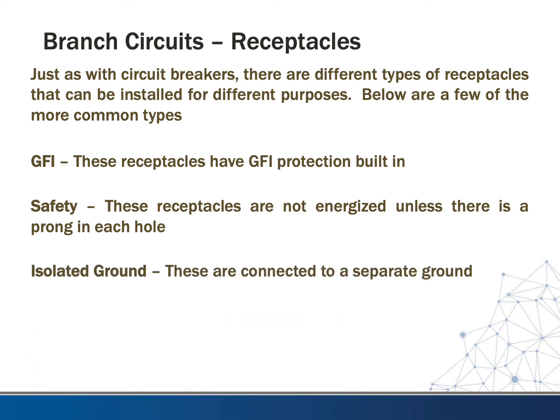Isolated grounds have a separate ground connection, different from the ground connections from other common loads. We develop two separate grounding systems — a noisy ground and a clean or quiet ground. This is used where you have a lot of noisy equipment, such as motors or electronic equipment. Some other equipment may not tolerate that noise very well, so we put in isolated ground systems for that.